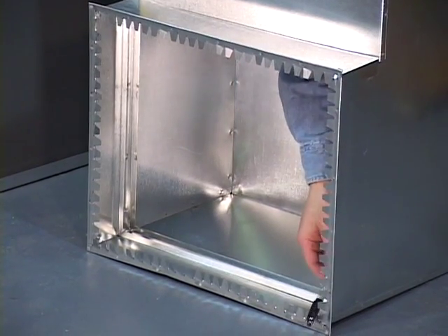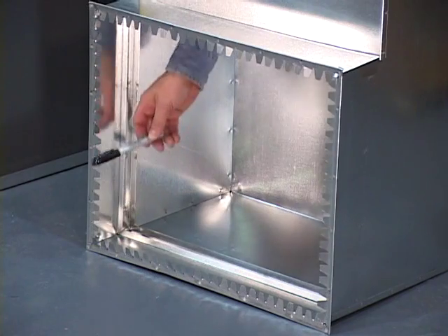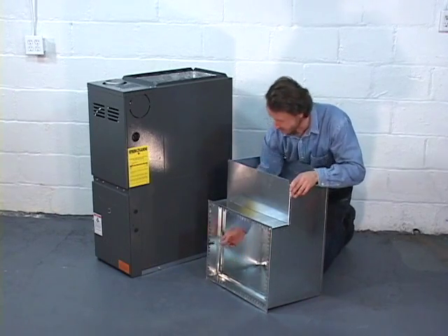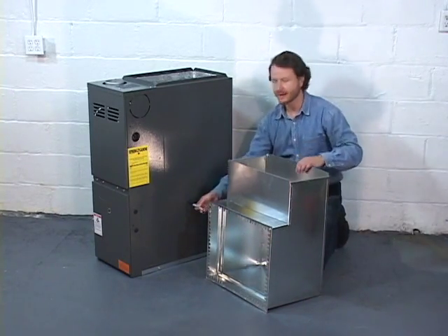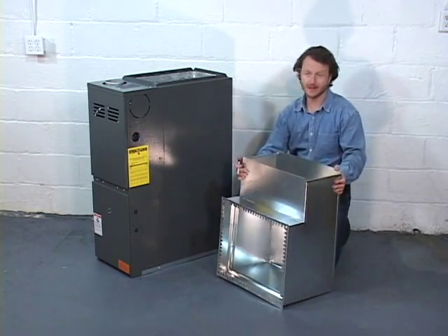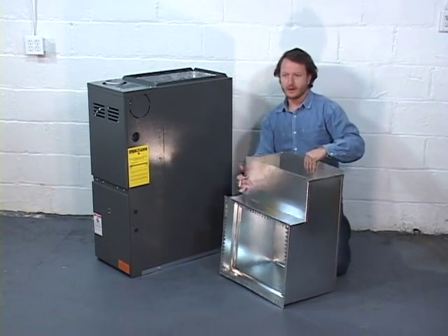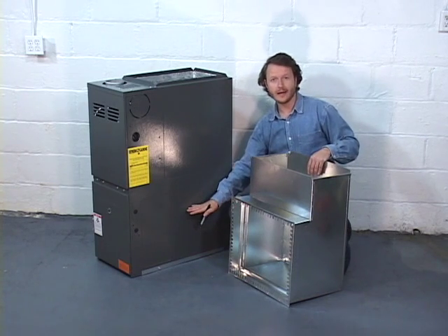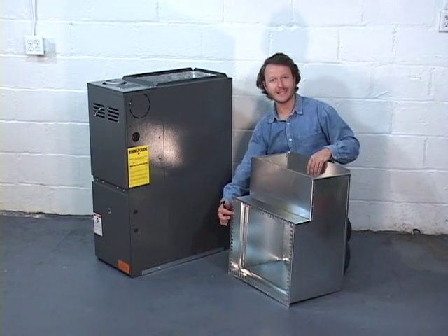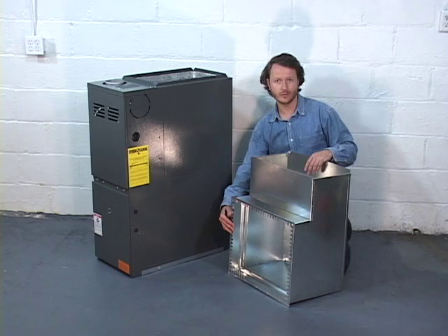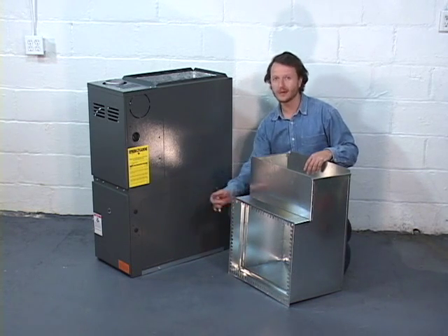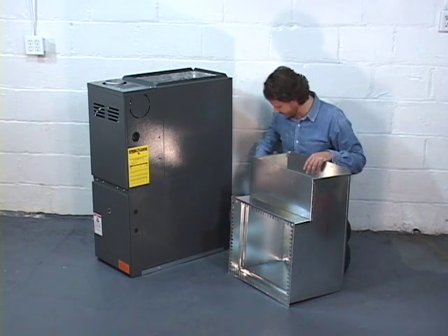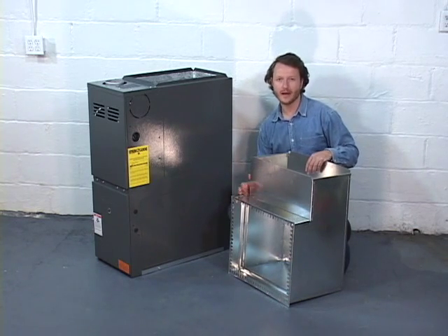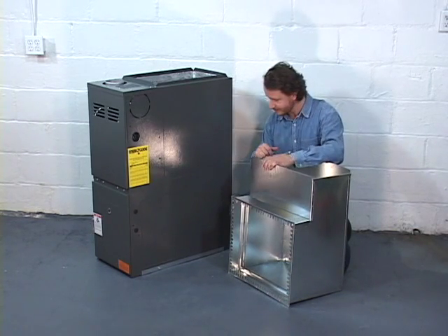This shape here will be marked on the lower side of the furnace, because we're going to cut a hole out in the furnace the same size as the inside of the return air shoe. Yes, you actually cut out the lower side of the furnace. Furnaces are designed to have that hole custom cut in it.